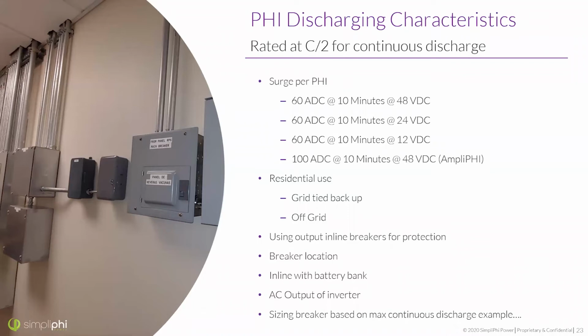The new AmpliPHI actually has an even higher discharge. It can do 100 amps at 10 minutes at 48 volts per battery. So just to give you an idea of what that is, that would be 5.1 kilowatts for 10 minutes per battery. So if you've got a bank of 4, it can do about 20 kilowatts for 10 minutes, actually a little over. So it can definitely handle quite a bit of surge.